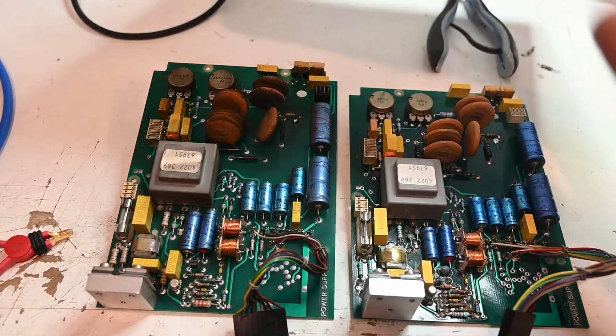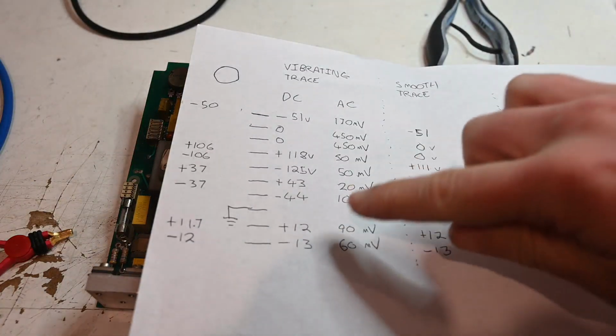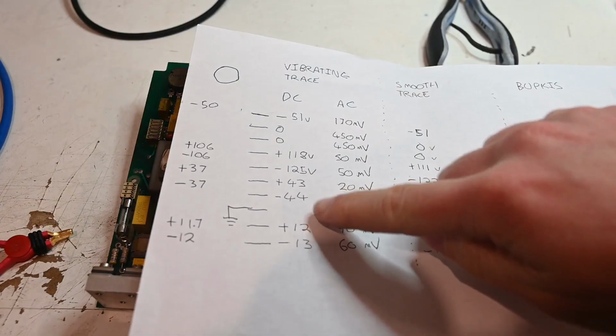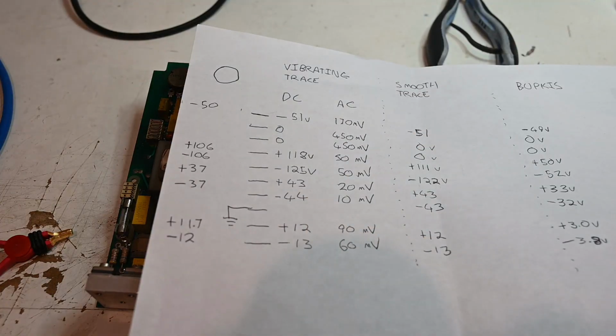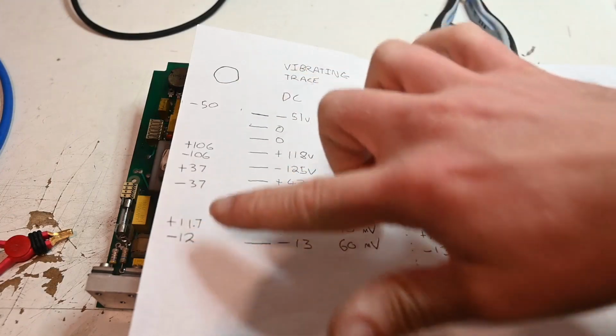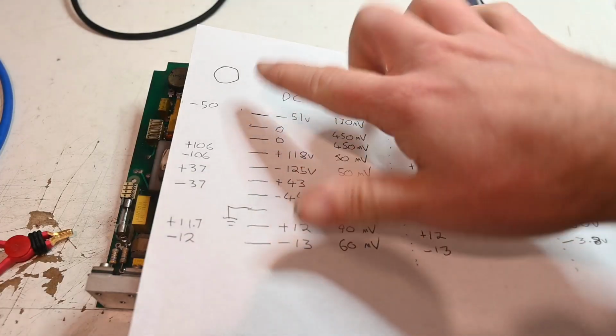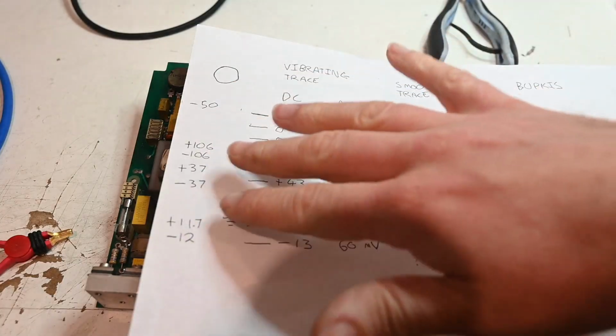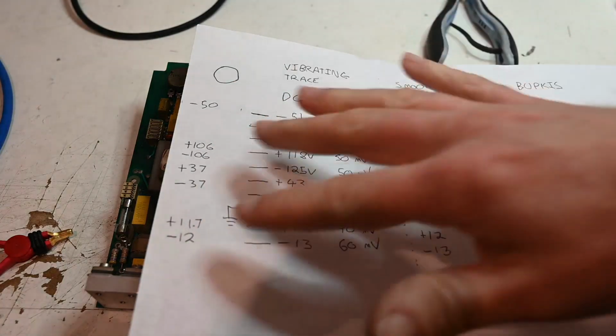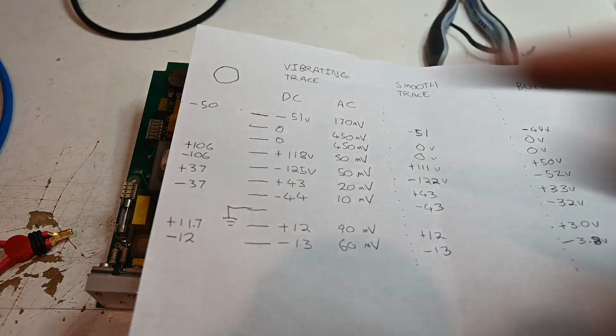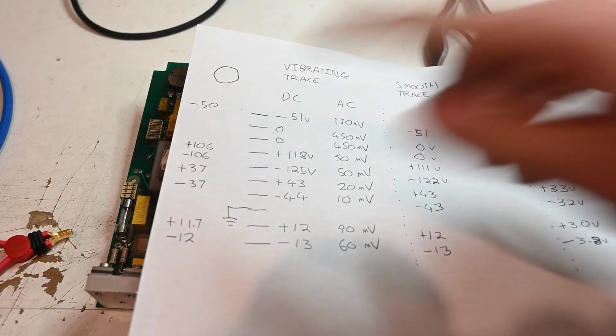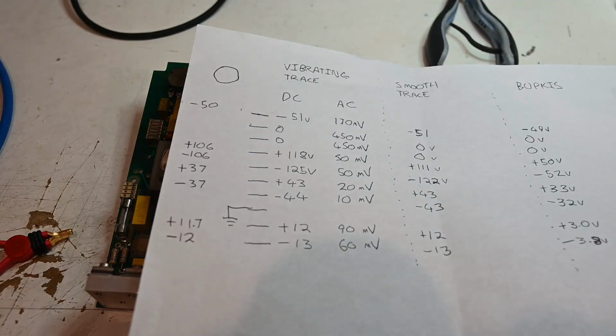Now another observation that I made is that when I added that resistor, all these voltages went up. So 44 became 48, 43 became 47. Now having measured the other unit, the good unit, that's definitely not a good thing. The voltages on that unit all read as being significantly lower. And I actually checked the manual for the PM5567, and these are actually very close. So that oscilloscope that we were talking about, the voltages it has in its power supply are very close to what we're seeing here. That's plus or minus 110 for those two rails. So I think we'll use that manual as a rough guide as to what we should be seeing in terms of the voltages for the time being.